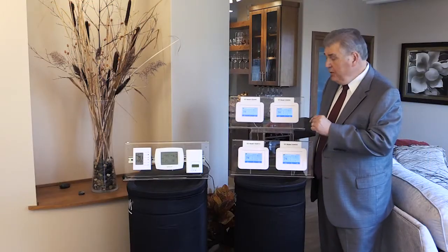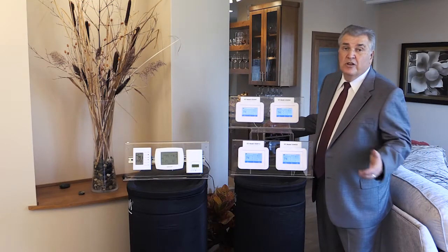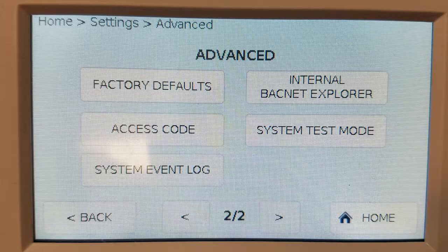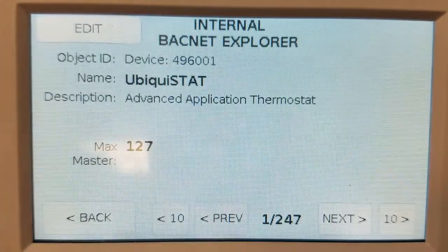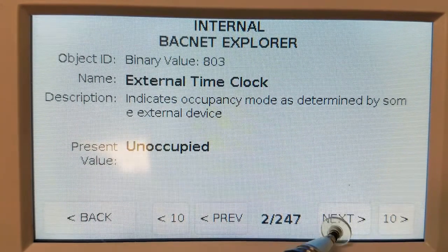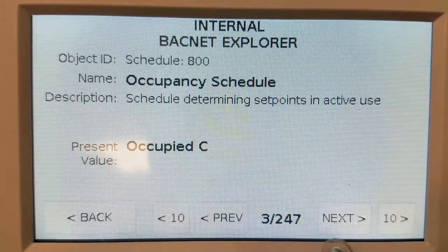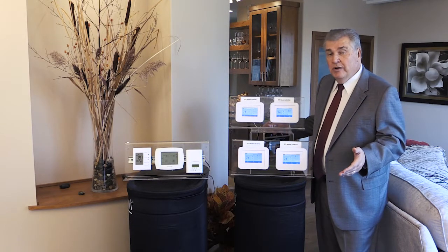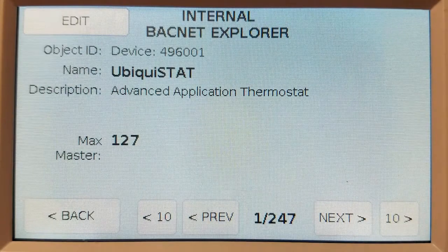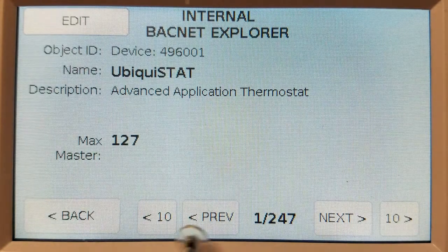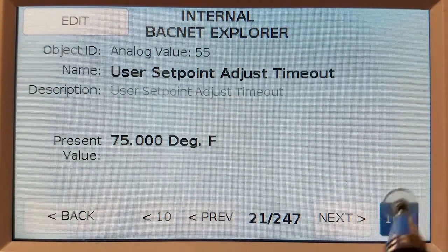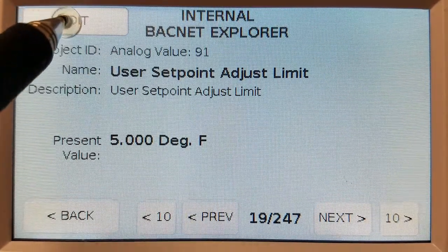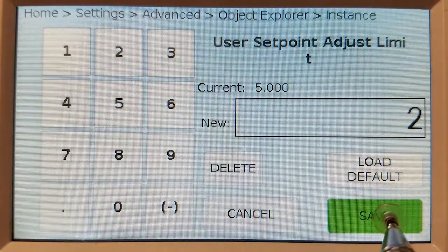And if you really need to get deep down into the Ubiquistat's programming, there's no need to hook it up to a laptop or fire up the software. Each Ubiquistat comes with a built-in BACnet Explorer, so every writable point is visible, programmable, and configurable — whether you're in BACnet mode, TCS bus mode, or standalone. For example, if you want to change the user setpoint adjustment so setpoints can only be adjusted by a couple of degrees, simply punch it up, press edit, make the change, and save it.